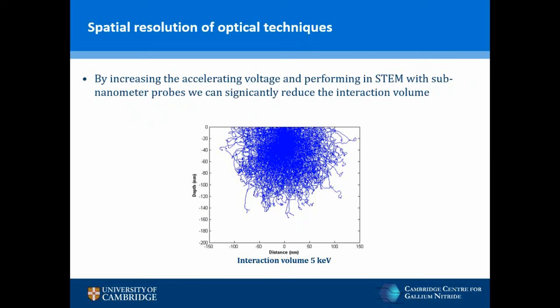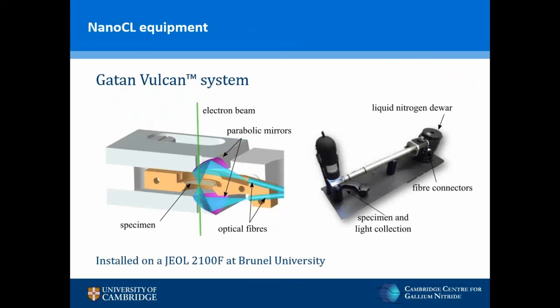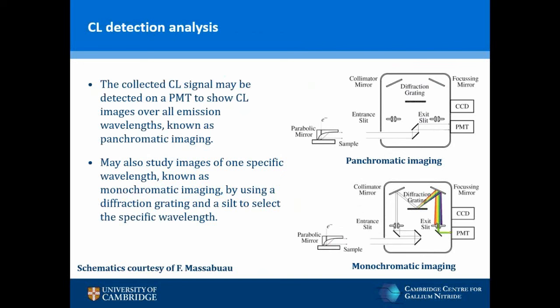To collect the CL signal, GATAN's Vulcan system uses mirrors attached directly to the sample holder in close proximity to the sample, providing a high collection angle with high detection efficiencies. The mirrors include a hole in the centre to allow the electron beam to pass through. The collected CL signal is then coupled to fibre optic cables that travel along the length of the holder to connectors at the end. The holder also contains a liquid nitrogen dewar to cool the sample. This system is installed on a JEOL 2100F microscope at Brunel University.